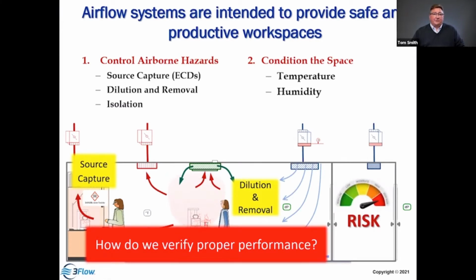and productive environment. And we're going to look first to capturing the hazards at the source. So that's where our fume hood comes in. We want to generate within the hood and remove those materials. But there may be materials that are generated inadvertently outside of a hood, and we're going to rely on the airflow in the room to dilute and remove those materials. So the two working together, the exhaust and the fume hoods and the general exhaust, plus the air supply, should be coupled so that they're working in tandem to help dilute and remove the materials to provide a safe environment for the occupants. And the need for airflow is going to be a function of risk. But we also simultaneously have to provide good temperature control and good airflow conditions for humidity and so forth. So it becomes very complicated to achieve these objectives simultaneously.